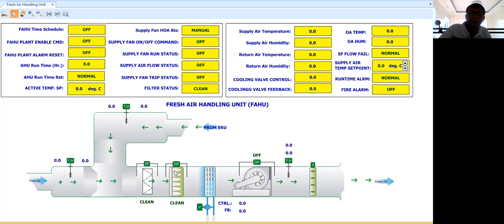The BMS engineer needs to determine how many cables need to be pulled to the fresh air handling unit. For the return temperature and humidity sensor you need a 4-core cable, another 4-core cable for the supply sensor, and another 4-core cable for the outside air sensor. For the valve actuator, since you are also supplying power, you need around a 5-core cable. For the damper actuator, for the differential pressure switches it is a 2-core cable each, and the fan will be controlled via the motor control panel.